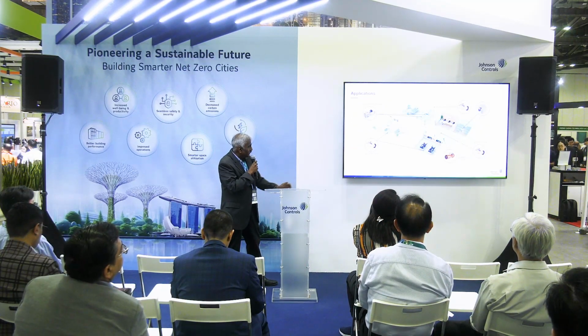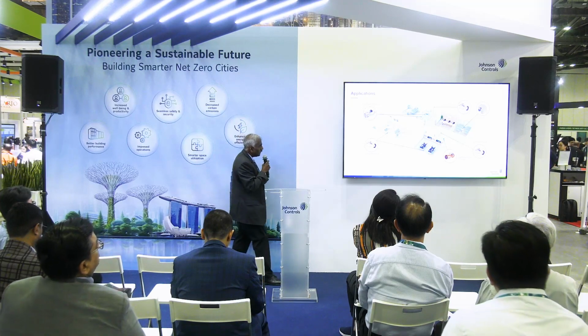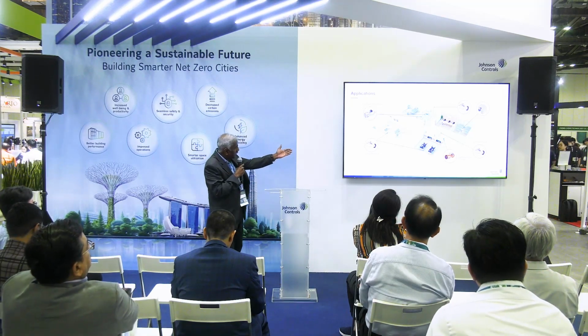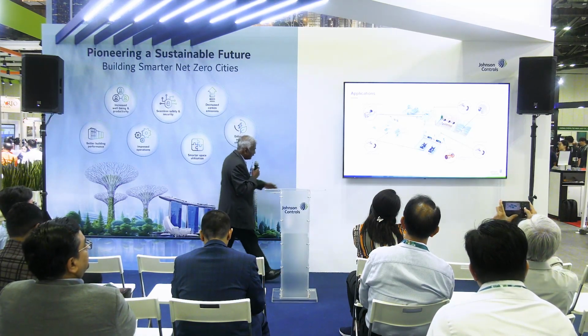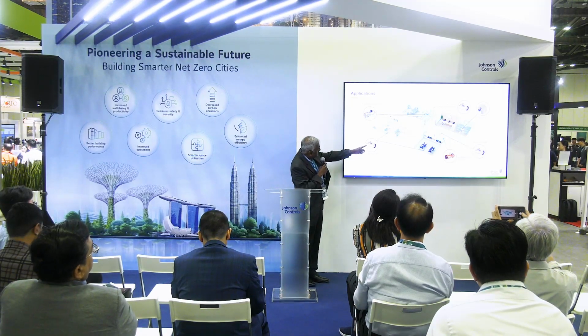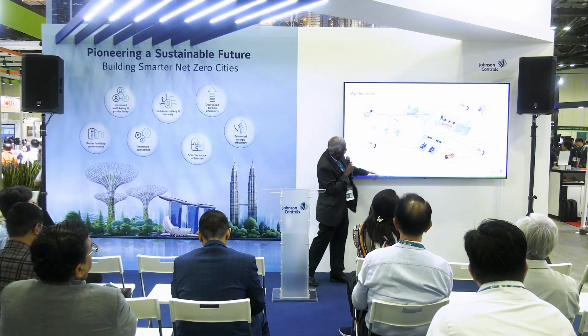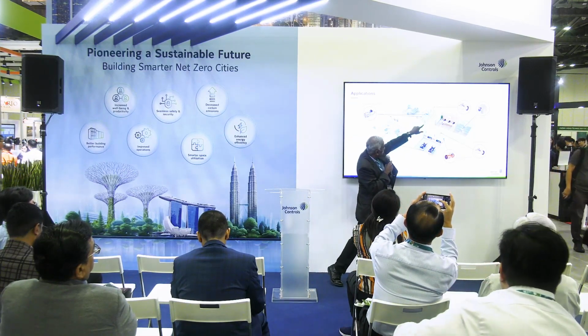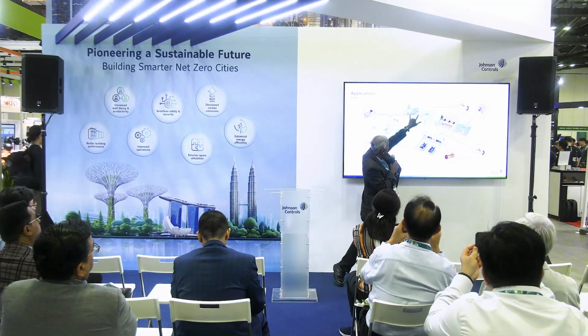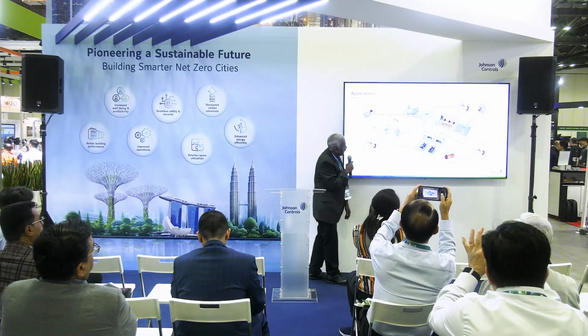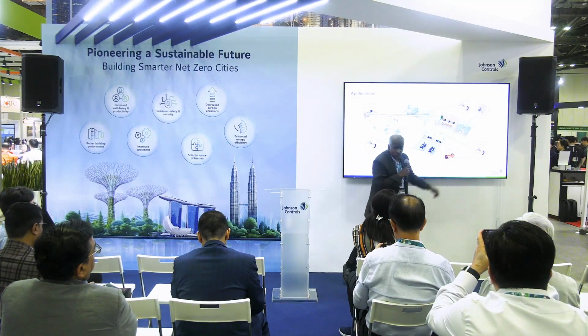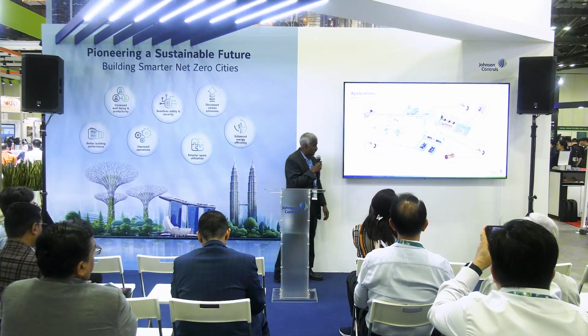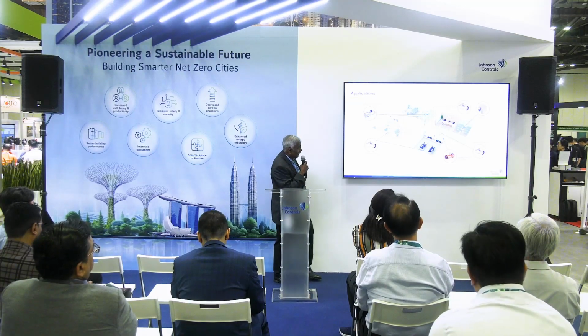So let's look at the applications. On your left, that's an operation theater - you can see a venturi valve at the supply and exhaust. Then you have the isolation room, and an NT room also. We have venturi valves to control the supply and the exhaust there. And here, that's where the VAV box is used - it's just a normal consult or waiting room. That's where we typically use the VAV box, we don't use venturi valves over there.